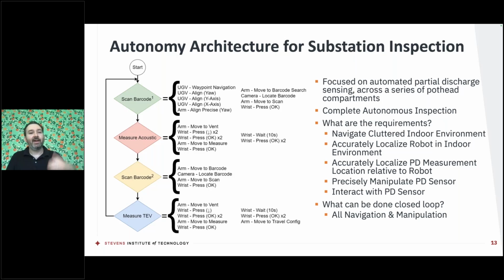And upon scanning that, we were able to collect the other two diagnostic measurements. In order to do all of that autonomously, we had a whole series of behaviors programmed into our robot, composed of two key steps. The first step was that the robot had to drive to the correct waypoint in front of the pothead compartment in the substation that it needed to inspect. Then it also had to align itself with the panel closely enough that it was able to reach up and begin taking these diagnostic measurements, which require physical contact with the panel.